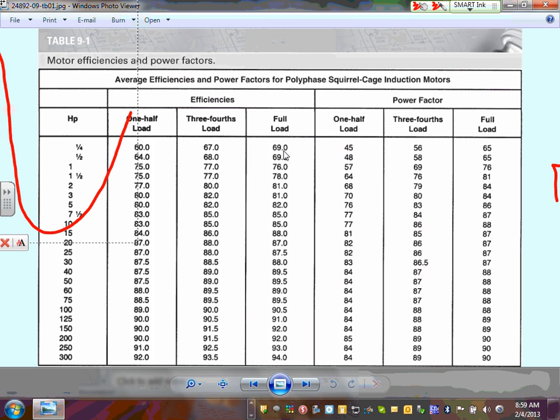Unless you have a VFD, of course. Unless you have a VFD, if you run it at half speed, half load, look at how screwed up it is. So for example, here's my efficiency 60, 67, 69 at full speed, power factor 45, 56, 65. So the efficiency and the power factor, guys, go up as the motor reaches its full speed. That's all you need to know about that one.